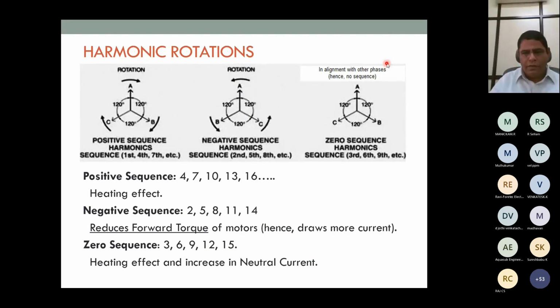So zero sequence harmonics are 3, 6, 9, 12, 15. It may not be the triplen series; there are some exemptions in the triplen series. These are specifically categorized as zero sequence. It has a heating effect and it increases the neutral current.